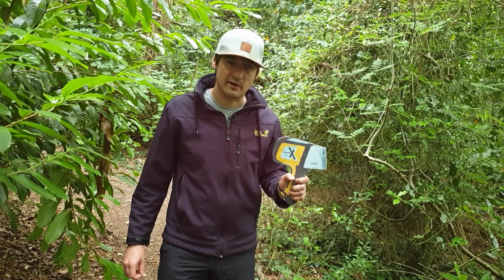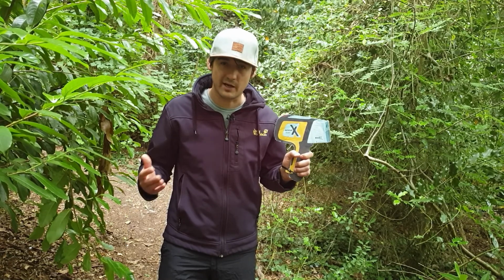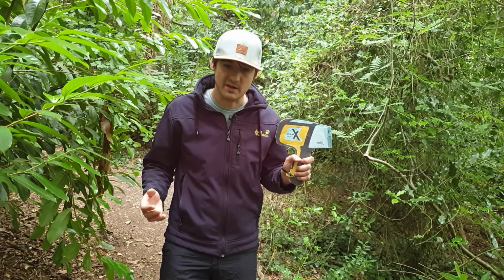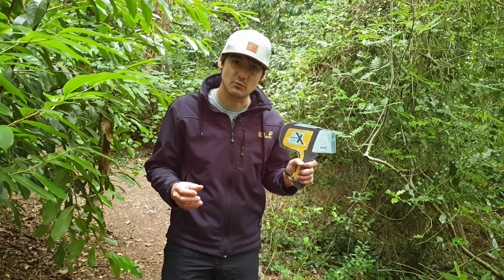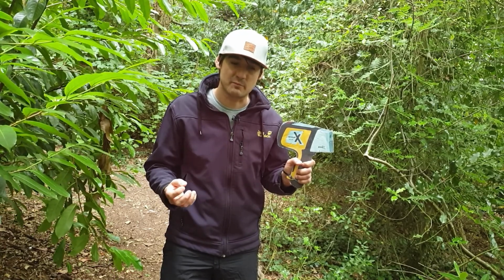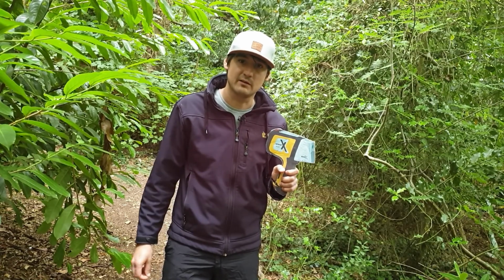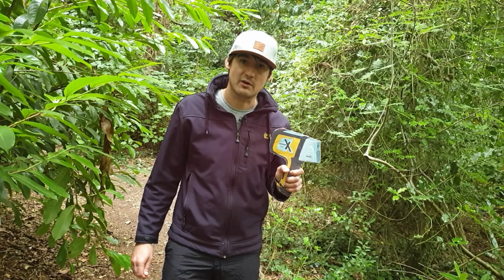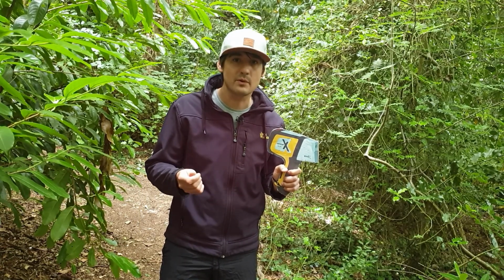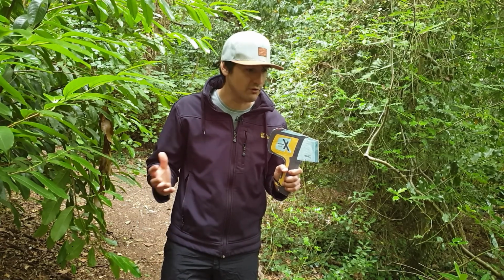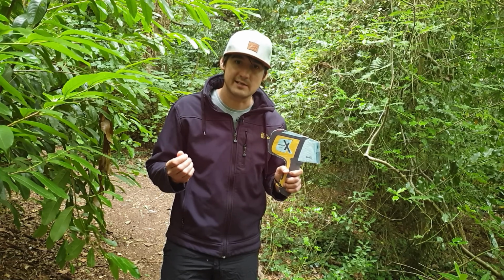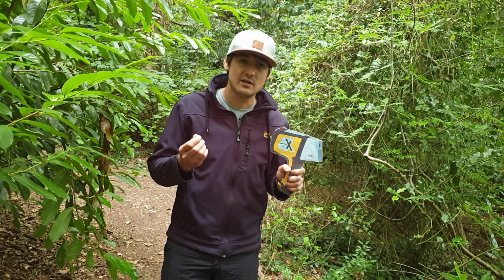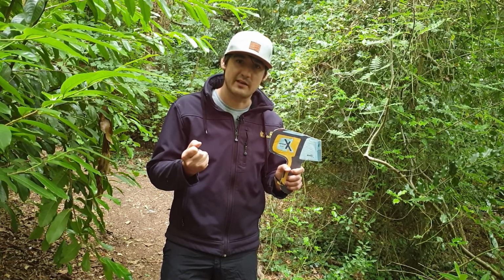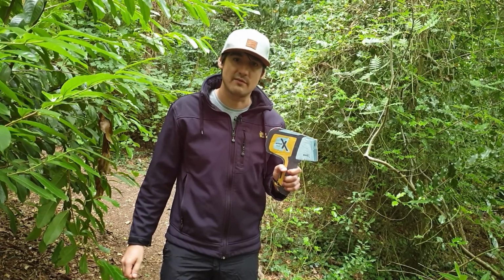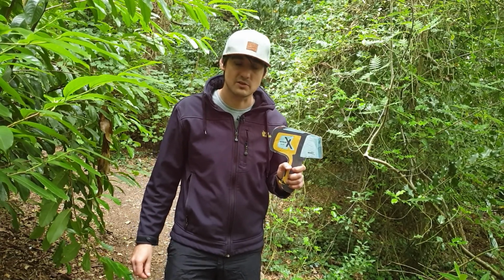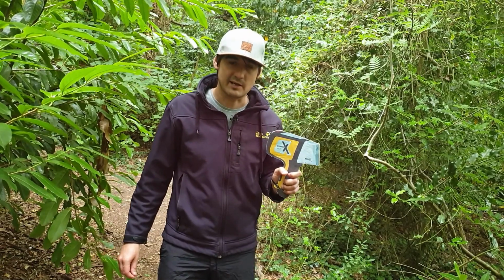One other note is that the XRF's worst enemy is water in the form of either rain or moisture in the soil. So never take an XRF reading on the bank of a stream close to where the soil is saturated with water, or particularly after it's just rained, don't take the XRF out into the field. Instead, you might have to wait a day or two for the soil to dry out. If the soil is slightly damp, just a little bit of dampness, that's okay. Often when you're in a woodland area like I'm in now, you can find that the soil will be slightly damp. That should be okay. What is not acceptable is if you can clump the soil together almost like a mud. Then that's too much moisture, and that will affect your analysis quite significantly. So try and keep the soil as dry as possible. Try and keep the XRF as dry as possible as well.